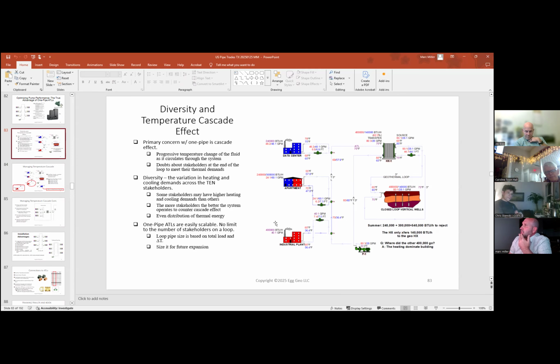Now you have to remember this guy here is not cooling, so it's not rejecting heat, but it is absorbing heat. And if we look back up at our heat exchanger, instead of 540,000 BTUs, we're only rejecting 140,000. Why? Because this guy consumes the 400,000 BTUs. So 540,000 minus the 400,000, you're only rejecting to the earth 140,000, because you're basically sharing the BTUs. Whatever energy these guys create that would normally be dissipated to the environment is actually being recovered and used by this stakeholder here at a reduced rate. So basically everybody would have a BTU meter, an energy meter, at each stakeholder's inlet to their home, or the outlet. It's actually the outlet because you would address the temperature drop. And so your costs are reduced for BTUs because you've already pulled the heat out of the ground. Now you're just circulating it through the loop.